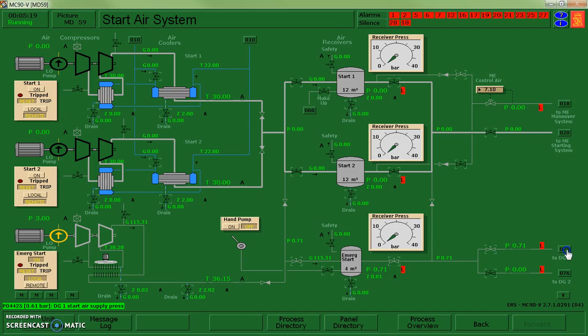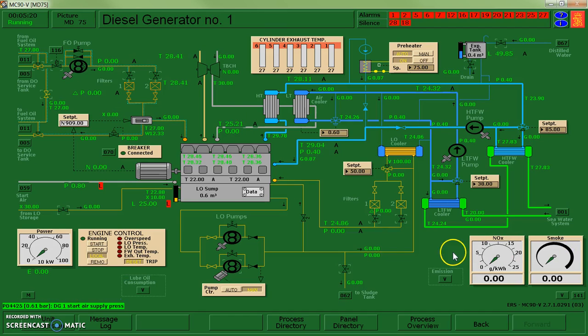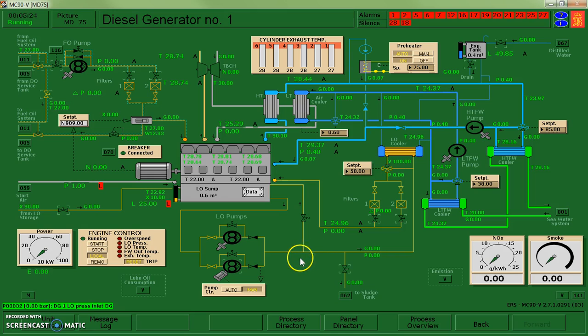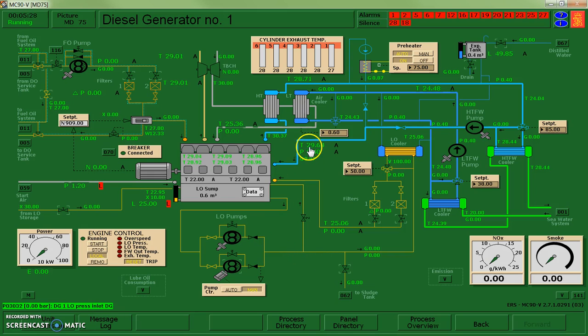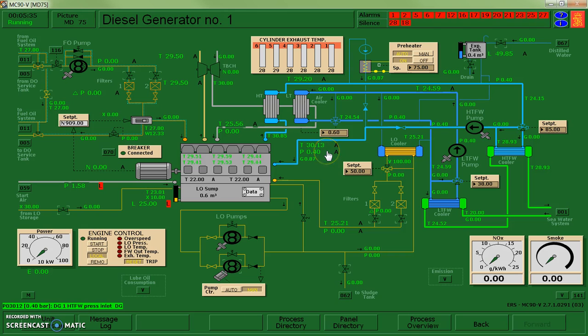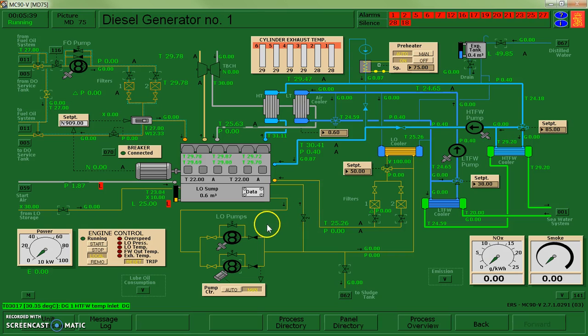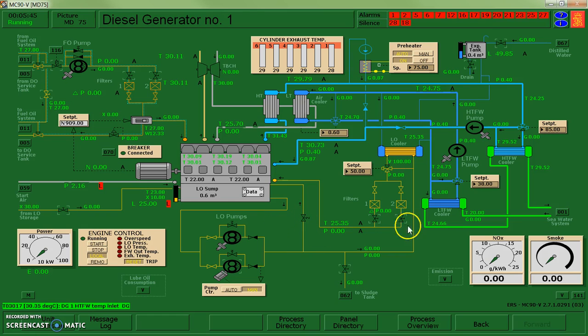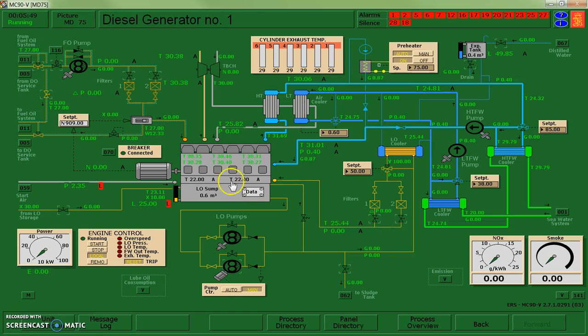So while I'm doing that, I'm going to come across to DG1. And I've got a number of systems that I need to get up and running. You can see my cooling water is doing okay. It's starting to warm up. So I'm up about 30 degrees. So I'm going to keep that warming up. So I've got three systems that I need to tackle now. Lube oil down here, my seawater system over here, and over here I have my fuel system.